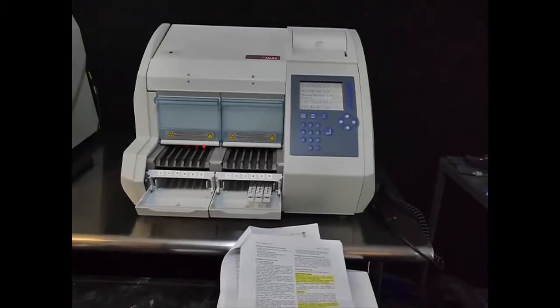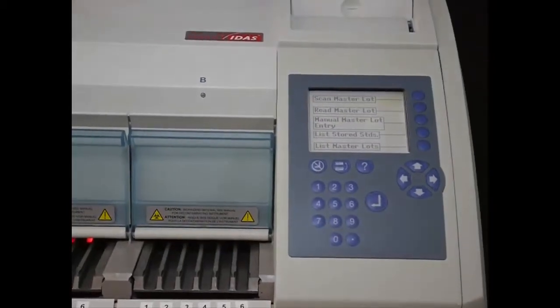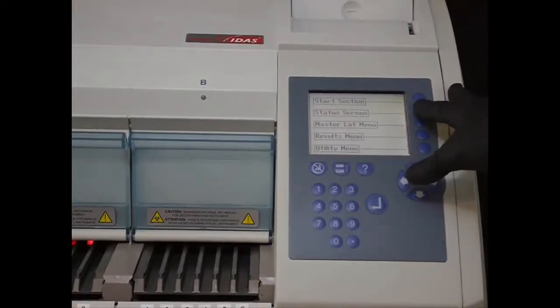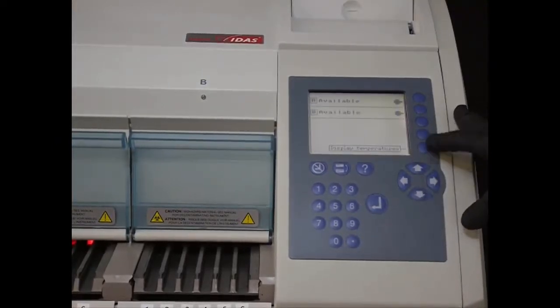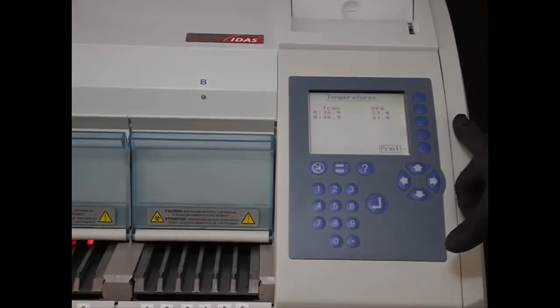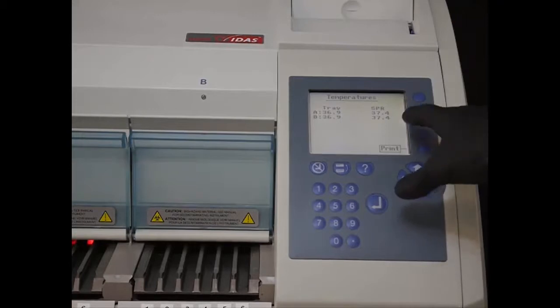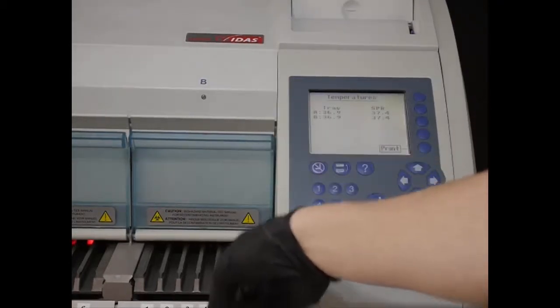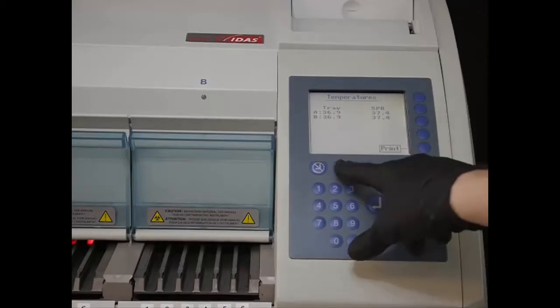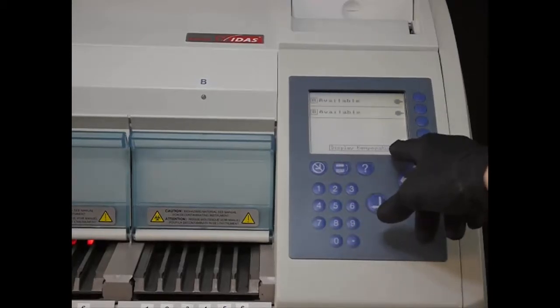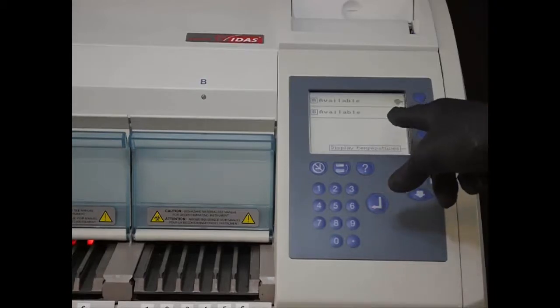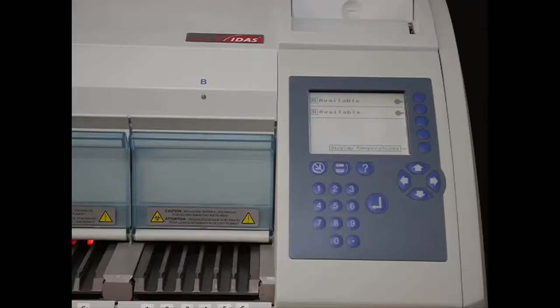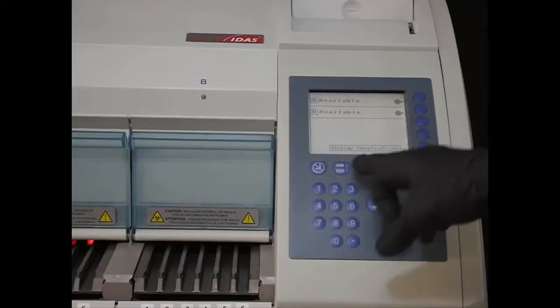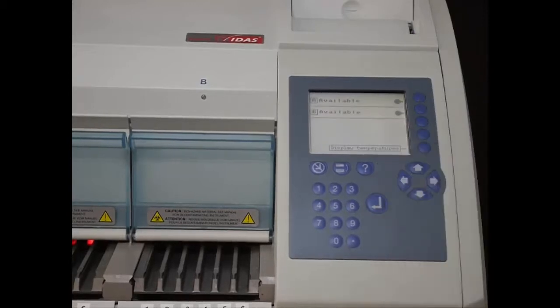First step will be to do the daily check through of the machine. To do this, we'll want to exit to the main menu and check temperatures via the status screen. You can see the display temps here. Ensure they're between 36.8 and 37.4. This is for section A, tray, and the SPR, and also for section B. Now that I know the temps are in range, I have both section A and section B available. If there is an error such as a tray jam, section B would show up on this status screen as an error state. Usually to correct an error state is a simple power cycle. You shut off, wait, and turn back on.